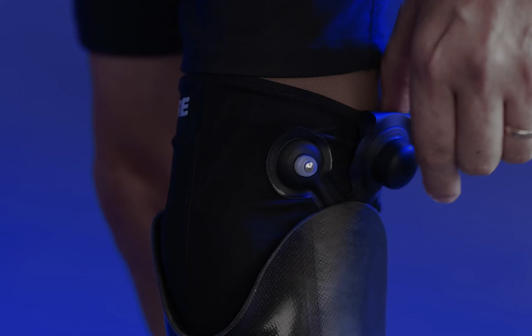The overlay is a new transtibial prosthetic device which uses air to manage the changes in the limb volume to address socket fit issues. It's composed of a thin, breathable fabric sleeve with an integrated air expansion system that can be adjusted by the wearer for maximum personalized comfort. The overlay goes over the liner and inside the socket, and a silicone print design inside the overlay ensures a snug fit with the liner and also prevents slipping.